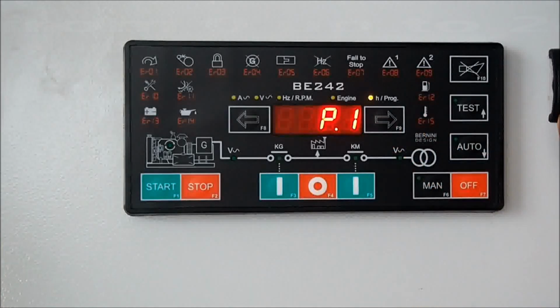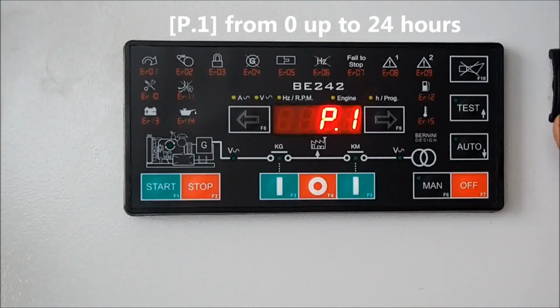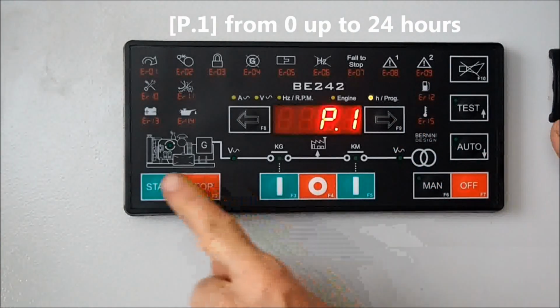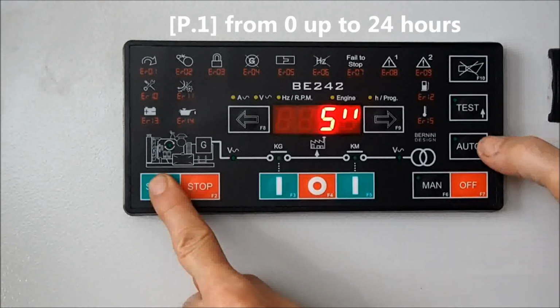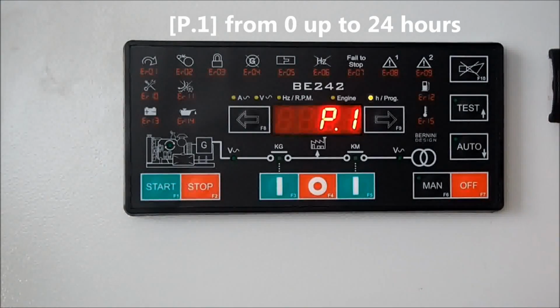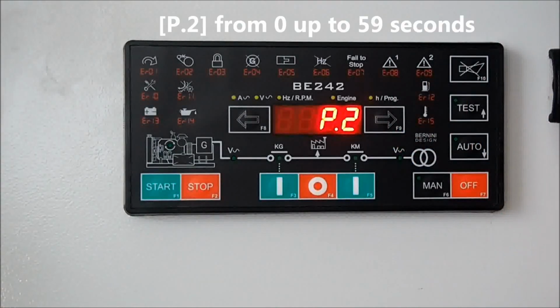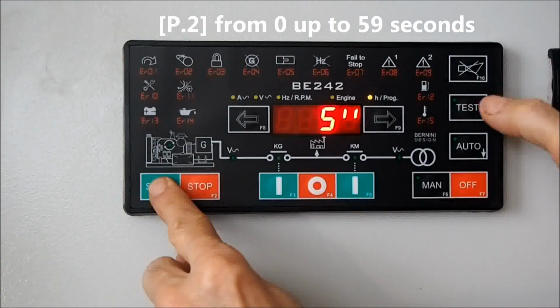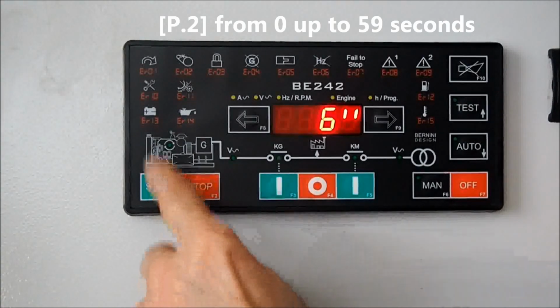Next parameter, parameter P1, that is the mains failure delay. Default is 5 seconds. You can put 4 seconds. Next parameter, P2, that is mains restore time. That is 5 seconds. You can put 6 seconds.